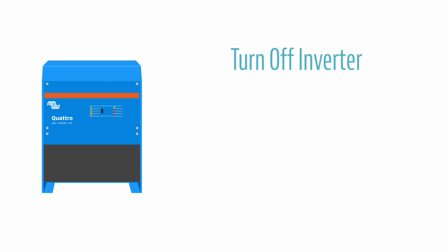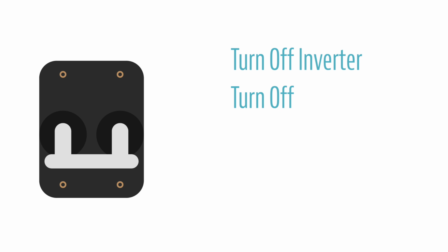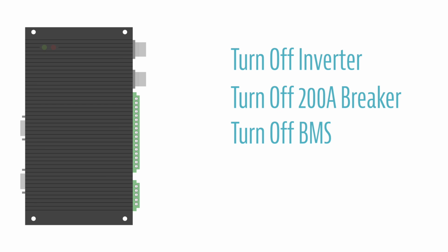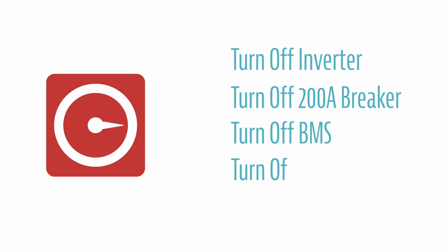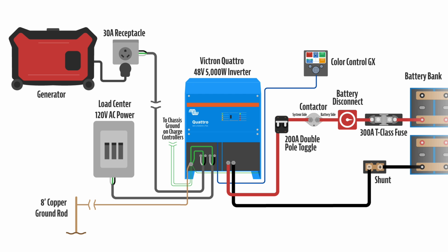Number 1, turn off your inverter. Number 2, flip your 200 amp double pole toggle. Number 3, turn off the BMS. And number 4, switch the battery disconnect off. At this point, you've already got your positive and negative trunk wires providing power to the inverter, and you've got your Victron cable going from the inverter to the Color Control GX. But there are still more connections we need to make.